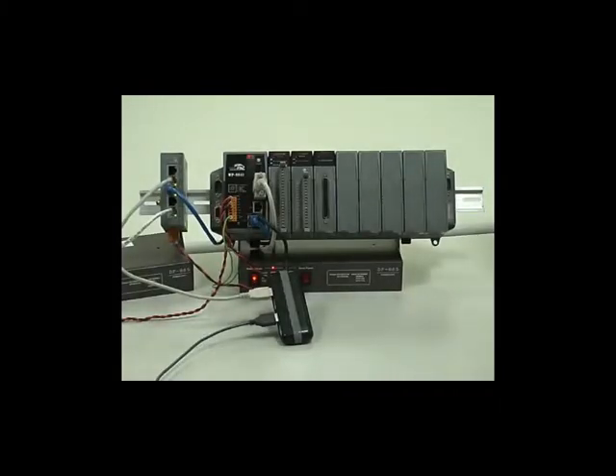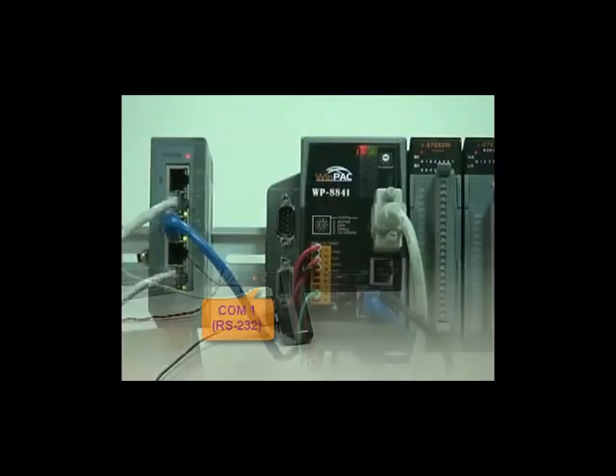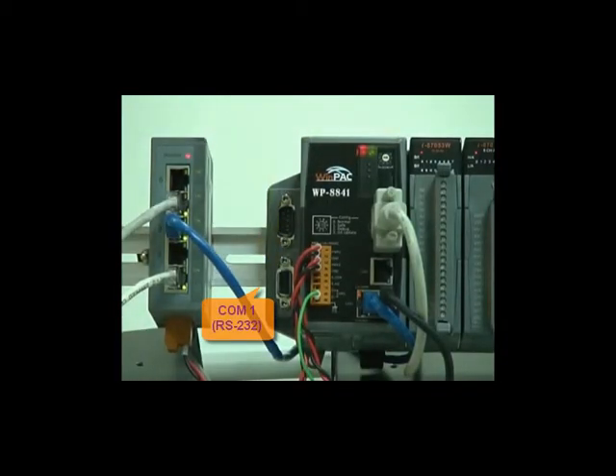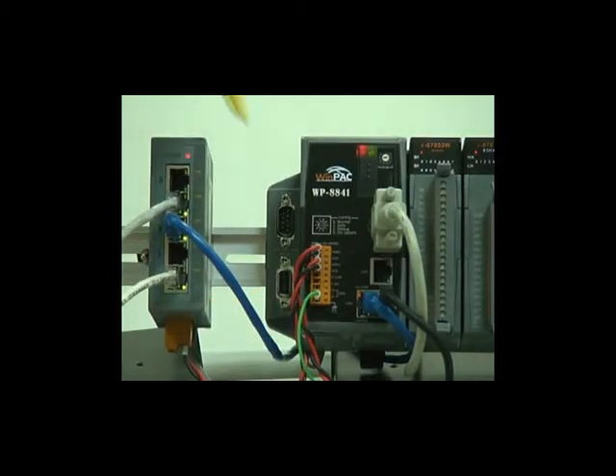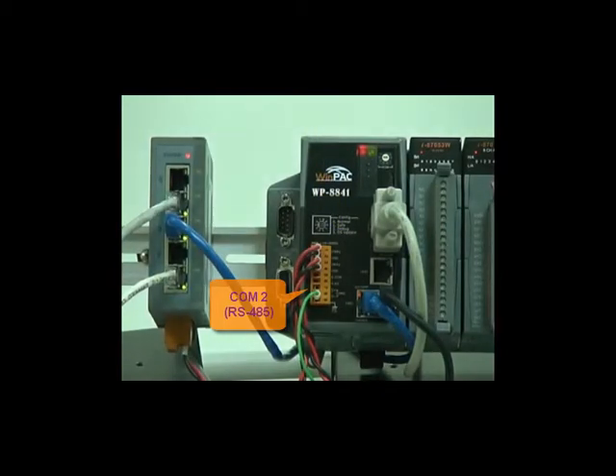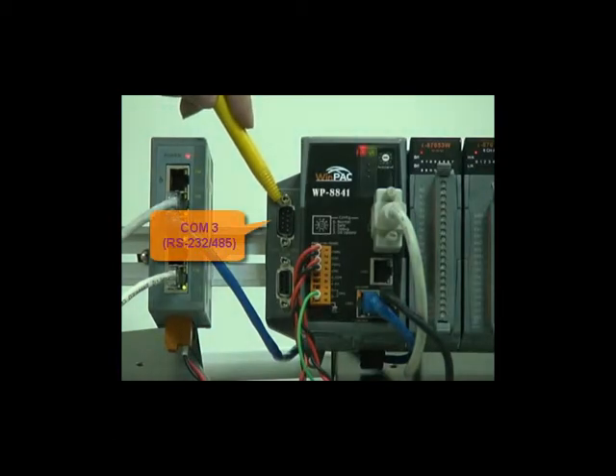Now let's go to the COM port introduction. On the lower left side of the outer shell is COM1, which allows WinPAC to communicate through RS-232. Under the main power is COM2, which supports RS-485 communication. Above COM1 is COM3, which can communicate through both RS-232 and RS-485.